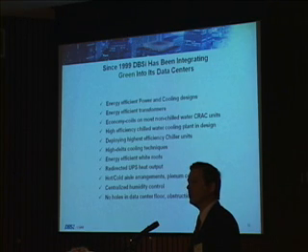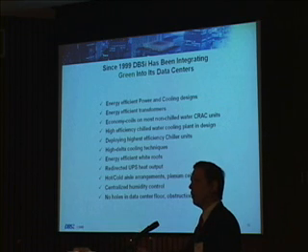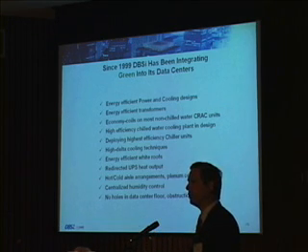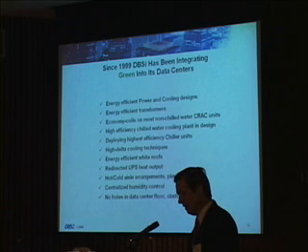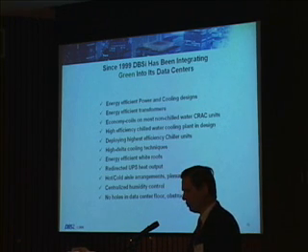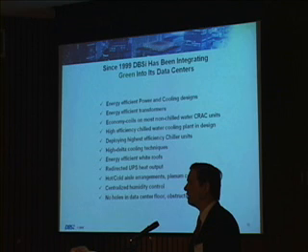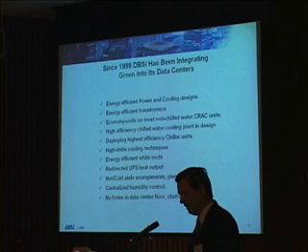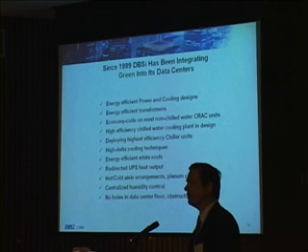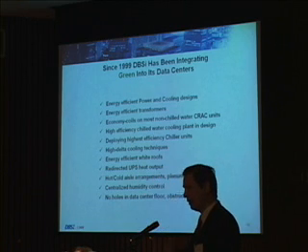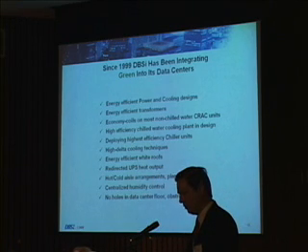So if you go to one of your step-down transformers and you feel the heat coming out of it, that's the energy being consumed by watts creating heat as it steps down the power. It's actually consuming power there. We put Econo coils on most of our non-chilled water CRAC units, meaning in the wintertime, we're not running our compressors. We're using the outside cold air to run through our CRAC units to cool them. We've deployed high-efficiency chiller units. High delta cooling techniques can only be done with that previous slide, where we're putting that hot air up into the plenum and bringing it through the CRAC unit at a hotter temperature than normal.